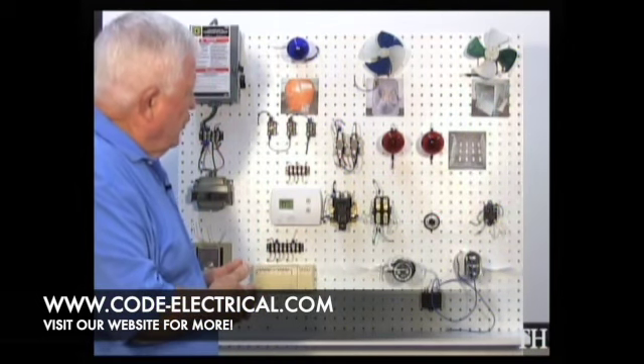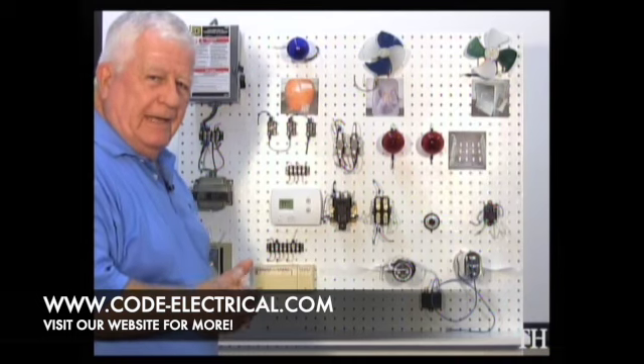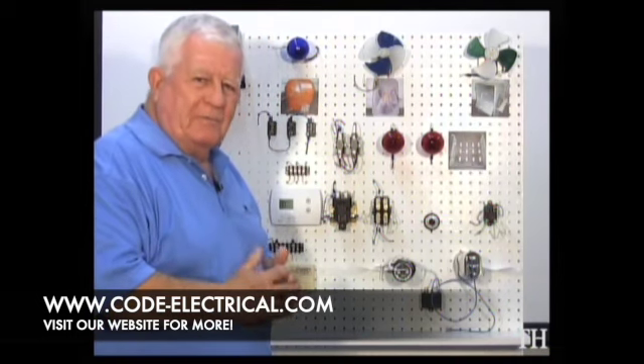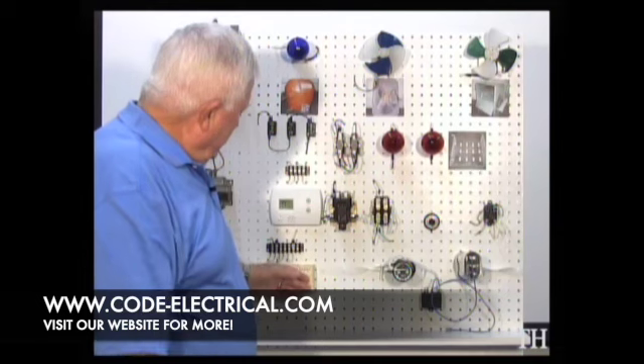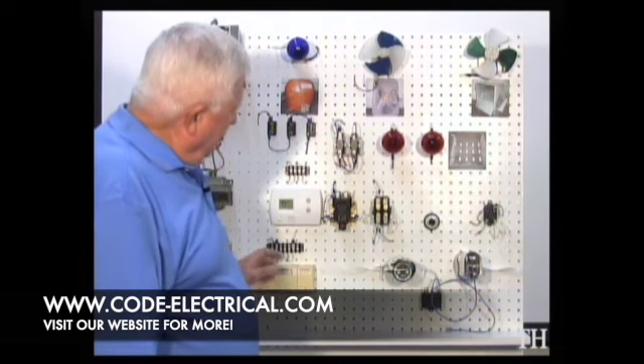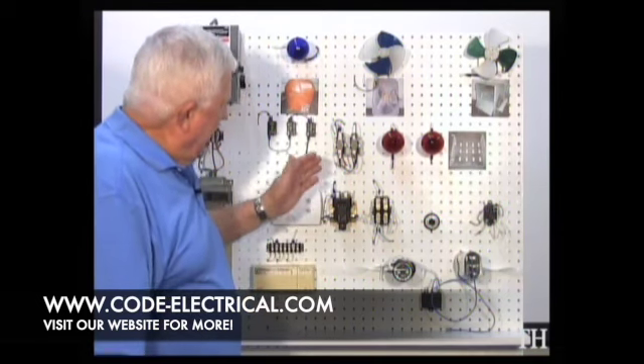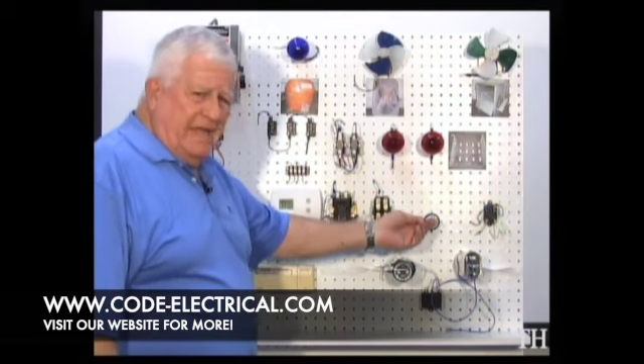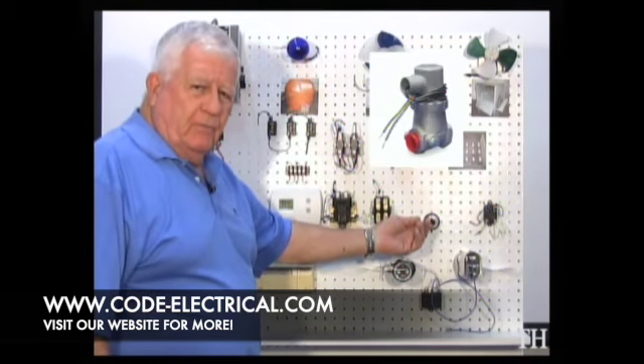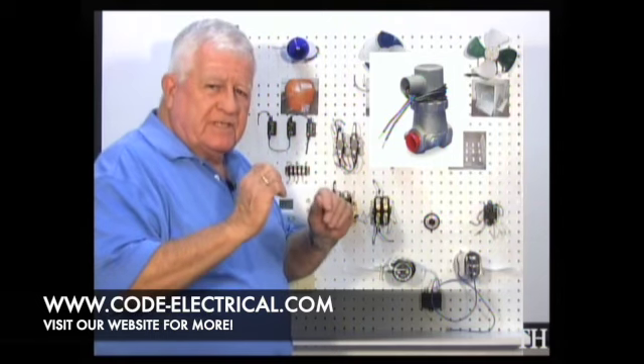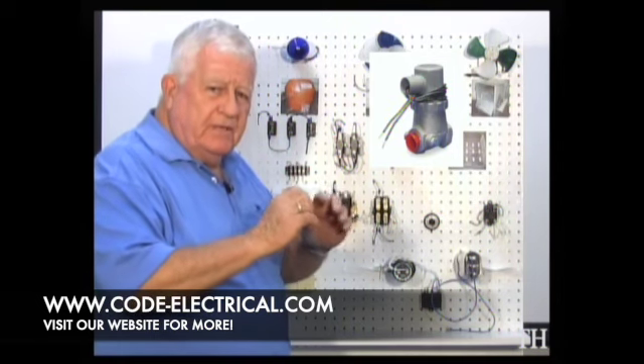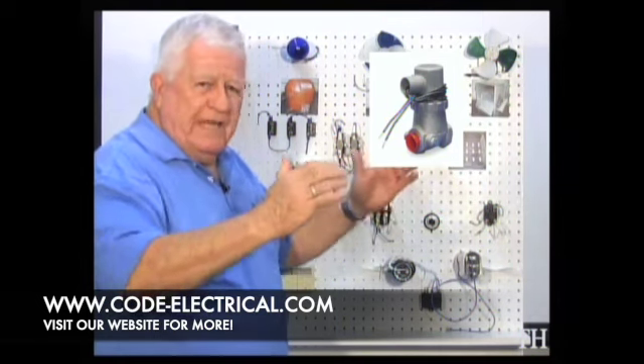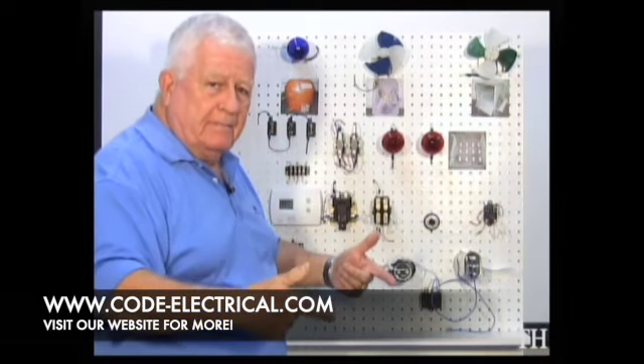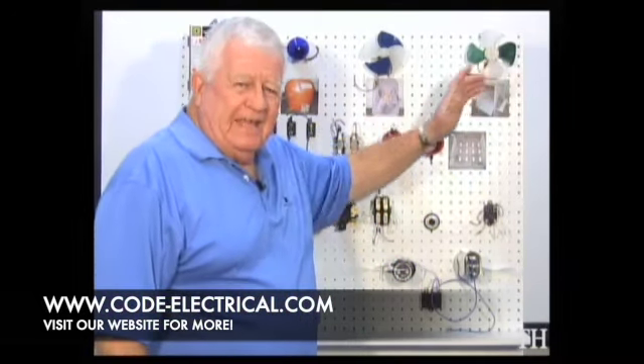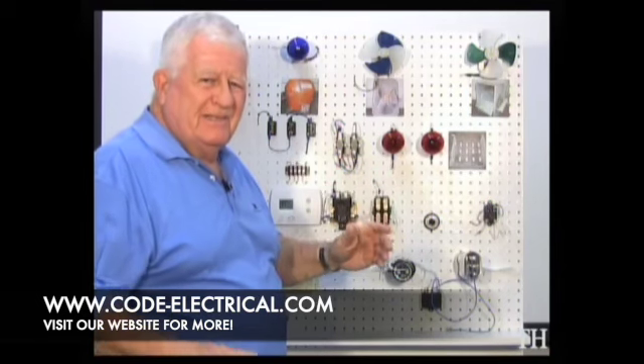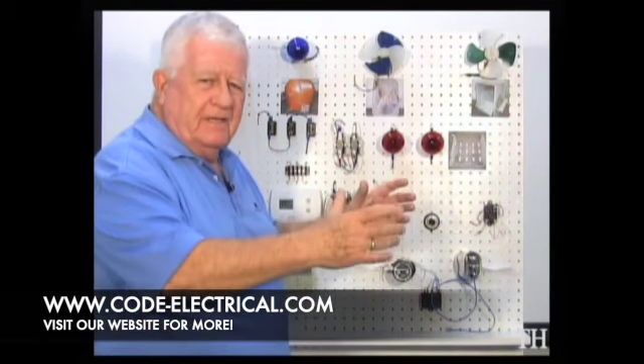When we get to heat, like say it's a cold day and we want some heat, I'm going to use this thermostat down here and I'm going to flip it, and what's going to happen, this light will be a gas solenoid. When it comes on, it means I'm sending a signal to the gas solenoid to ignite, and your heat exchanger will start heating up. I don't want the fan to come on yet. Why? Well, it hasn't heated up enough, the heat exchanger.